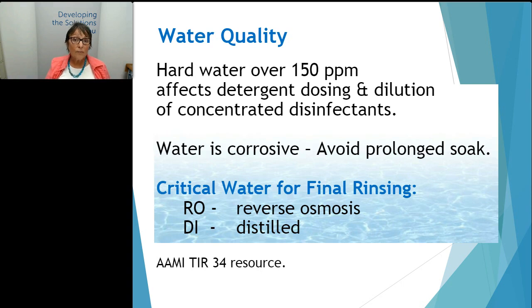The hard water binds up some of the detergent and makes it less effective. So then you may have to increase dosing, at least slightly. And you may have to consult with the detergent manufacturer to find out if it is even okay to dose higher because of the hard water. And interestingly enough, if you use concentrated water-based disinfectants, hard water can also affect the dilution and effectiveness of concentrated disinfectants if the water is too hard. So that is a very important issue.